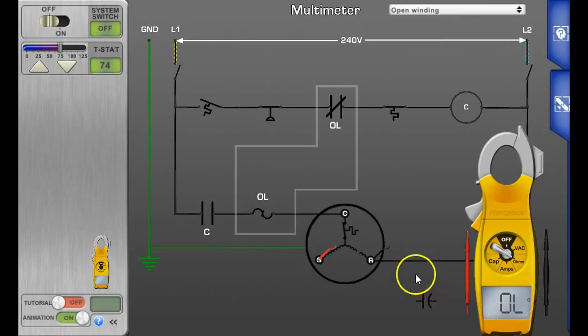That's open as well. Now let's take a look at start to common—we have 10 ohms. So we know that the start winding is good, the run winding is open, and you will have to condemn this compressor.